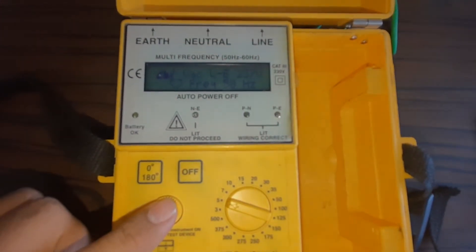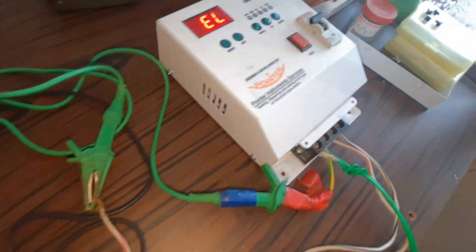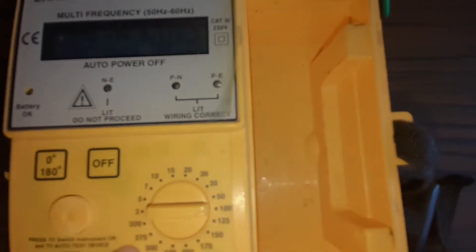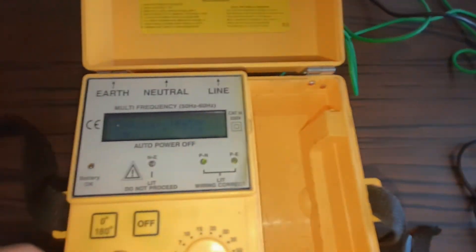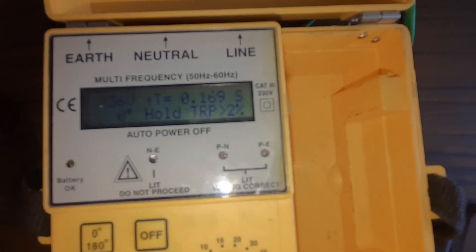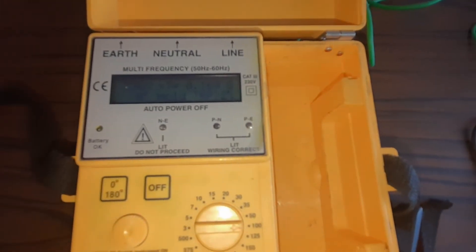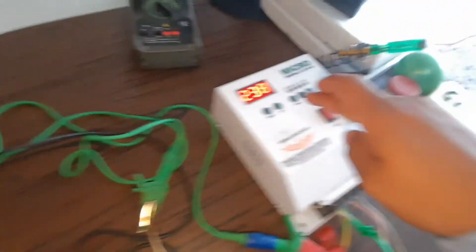When we press for 5 milliamps, the tripping time has decreased to 0.113 seconds. The earth leakage is created. Now if we inject more - beyond 100 milliamps - we can further test for 100 milliamp leakage to see how much time the ELCB takes. We press and 0.169 seconds is taken to trip the ELCB. This is the test procedure for how to test the ELCB from an ELCB tester.